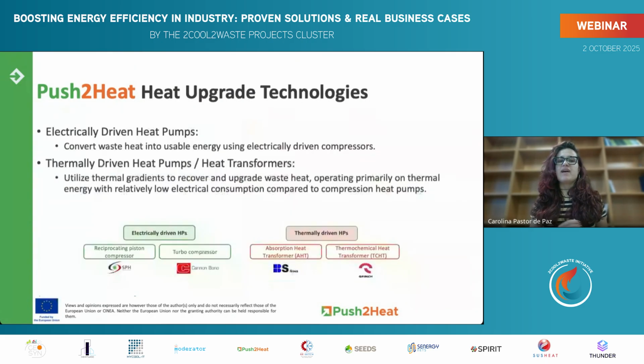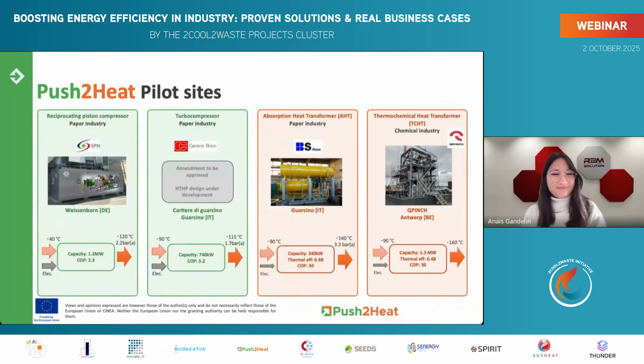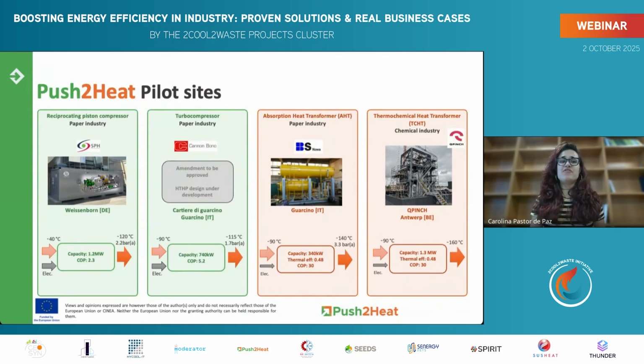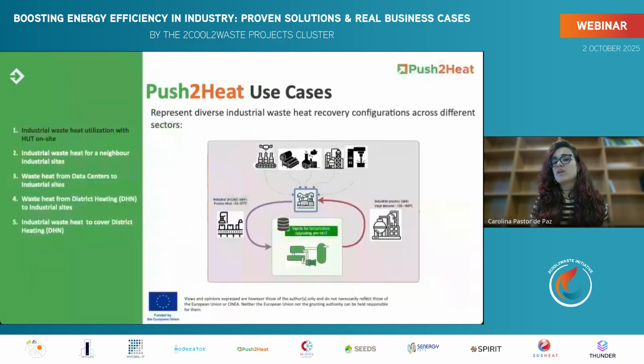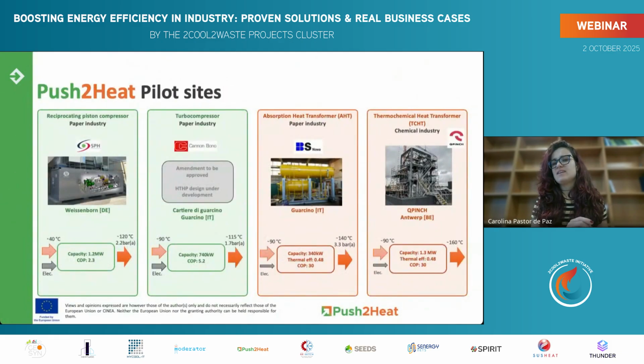These technologies have been applied into 4 main pilot sites. The first, a piston compressor, has been installed in a paper industry, recovering heat from 40 to 120 Celsius degrees. The next, still being defined due to an amendment, will be a turbo compressor for a paper industry that will recover heat from 90 to 115 Celsius degrees. Then an absorption heat transformer for paper industry will recover from 90 to 140 Celsius degrees with lower electricity consumption. The last one is a thermochemical heat transformer that will be installed in a chemical industry.